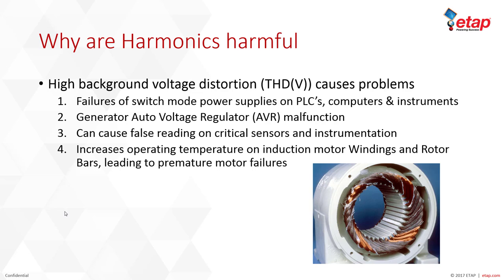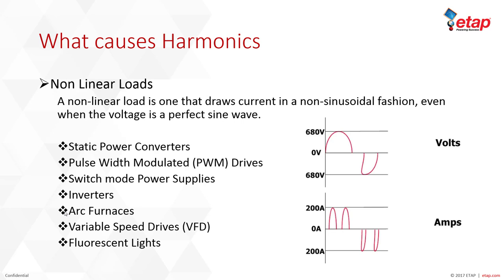What causes harmonics? As mentioned earlier, it's because of nonlinear loads. A nonlinear load is one that draws current in a non-sinusoidal fashion even when the voltage is a perfect sine wave. The illustration shows the voltage sinusoidal wave, and on the bottom, because of the chopping that happens in power electronics, you have the distorted current. Nonlinear loads typically include static power converters and pulse width modulated drives, or PWMs.